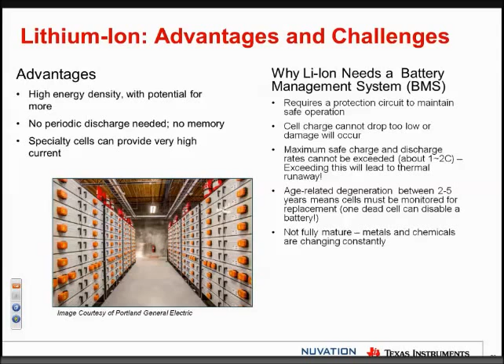This is typically done in multiple levels. First and foremost, a BMS should intervene and prevent the system from getting anywhere close to a critical state, typically by gently ramping things down as it anticipates approaching some limit—that's the gentle control. But if it detects that isn't taking effect, or there's a sudden transient causing a problem, it can very rapidly pull all the batteries offline. That's the second level that prevents you from going into a critical runaway state.